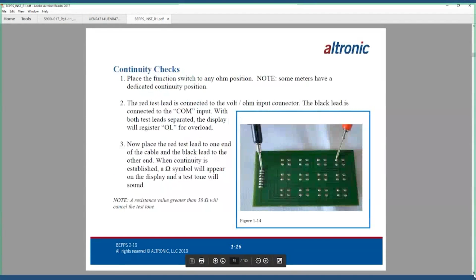So continuity check. Now, if I'm just troubleshooting an electrical circuit that's supposed to turn something on or off, continuity check and the voltage check are probably my two favorites. I don't get in much to actually measuring resistance, and I hear guys out in the field always measuring resistance. What I like about the continuity check is it's just a quick check. If I'm in a quiet area where I can hear, or sometimes you'll see me out in the field, if it's a noisy location, I'll hold my meter like an old telephone between my shoulder and my ear, and when you touch the two probes together, you'll hear your meter buzz.